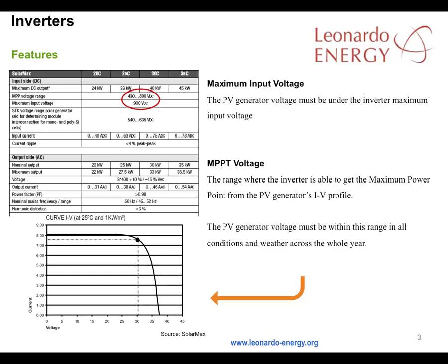You must also consider the maximum power point voltage. The MPPT voltage is the range in which the inverter is able to get the maximum power from the PV generator's IV profile. The IV profile is a graph of current versus voltage from a PV generator as the load increases from no load to maximum load voltage. The PV generator's voltage must be within the MPPT voltage range in all conditions and weathers across the whole year.